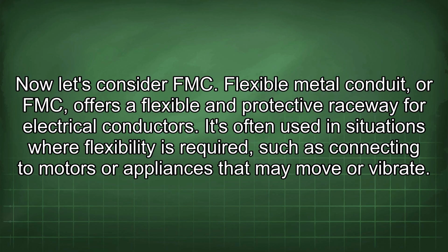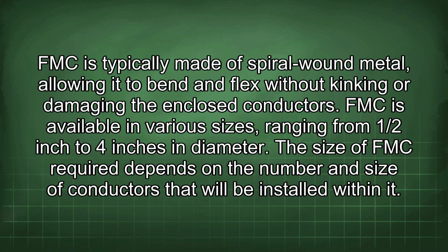Flexible metal conduit, or FMC, offers a flexible and protective raceway for electrical conductors. It's often used in situations where flexibility is required, such as connecting to motors or appliances that may move or vibrate. FMC is typically made of spiral wound metal, allowing it to bend and flex without kinking or damaging the enclosed conductors. FMC is available in various sizes ranging from 1/2 inch to 4 inches in diameter. The size of FMC required depends on the number and size of conductors that will be installed within it.